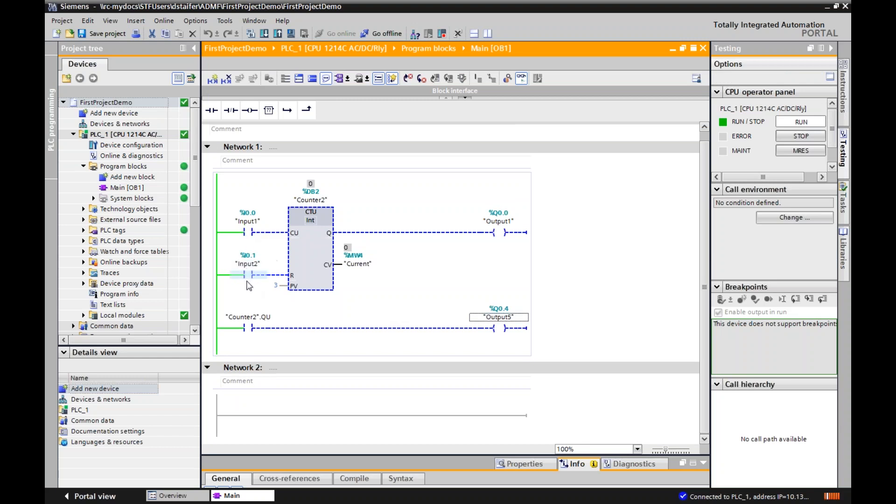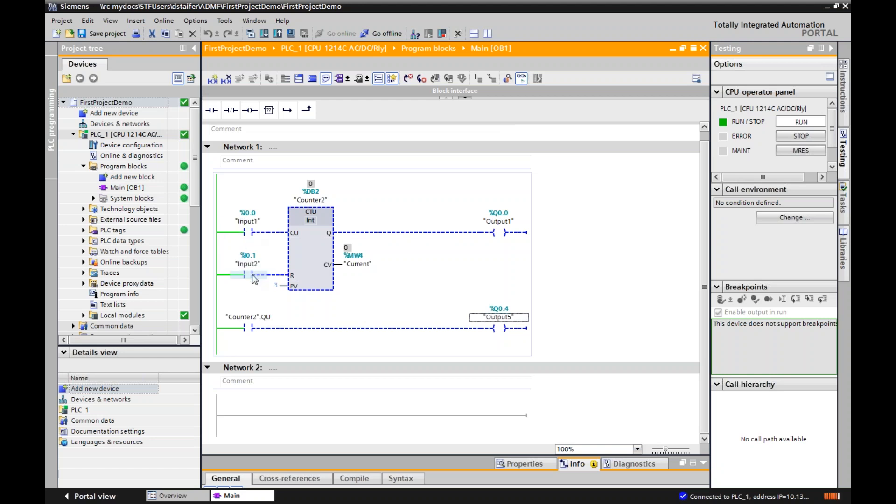You can see when these are false, this automatically starts at 0. Be careful, sometimes if you're having this draw from other areas, it may not reset. Good practice is always reset your counters when you first are doing something new or set it to a state that's always the same, so you can keep things safe and runs predictable. Here's my input 1, input 2. If I toggle input 1, you can see now in both above the counter and in the current value, that goes up to 1.